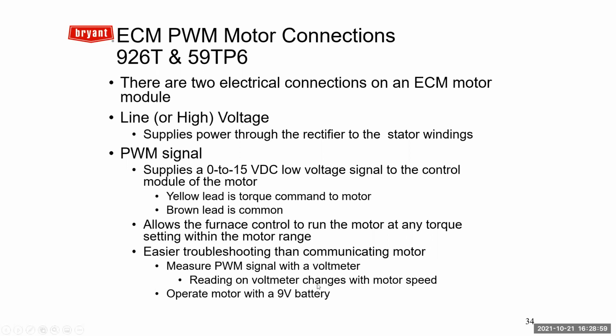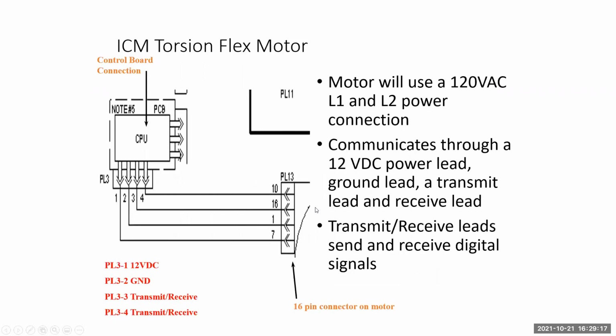Your readings on your voltmeter will change with motor speed. You can dummy your motor: put jumpers on yellow and brown with a 9-volt battery, and that motor should run. Again, the motor will use 120 on L1, L2, and then 12-volt power supplied. Down here, it'll show you on your ICM torsion motors what plug does what. 3-1 is 12 volts, 3-2 is ground, 3-3 and 3-4 are your transmit and receive.